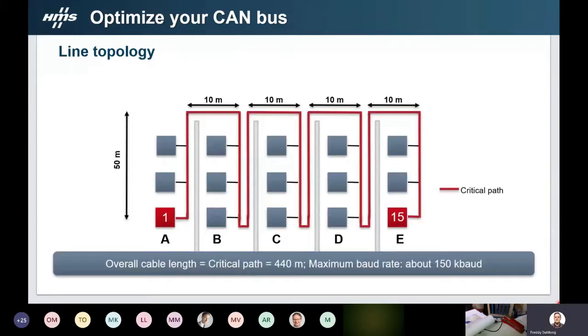Let's look at line topology in this example. Maximum bitrate on CAN is defined by the distance in meters between the most distant nodes. In this case, node 1 and node 15 are the furthest away from each other, creating a critical path of 440 meters. The maximum bitrate you can use is 150 for this length of cable.